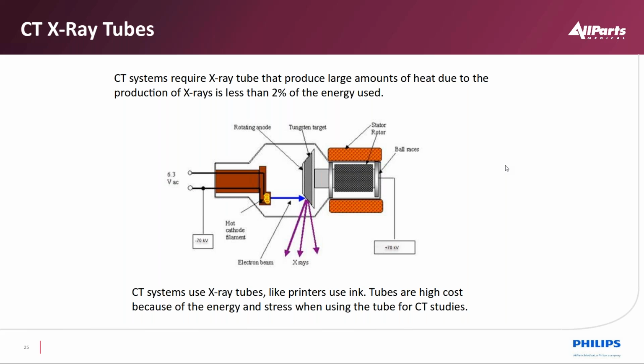So obviously, instantaneously in that same amount of time, we have to have a bigger anode target to dissipate the heat. The focal spot and the angle of the target would stay the same, but the tube diameter would get bigger because we're trying to spread that heat load out over the target and then move that heat load off, either through air cooling, and then most of these systems are oil cooled. So we're spinning that tube at anywhere from 8,500 RPM to 10,000 RPM. So we're spinning that anode that much, and this whole assembly is being spun around the patient as well. We're showing a single filament here, but we'd have more filaments as well.